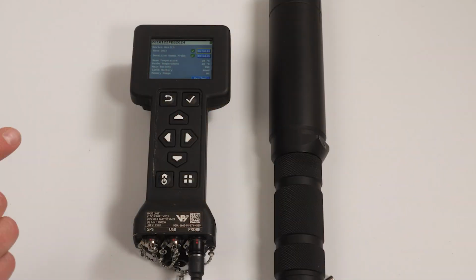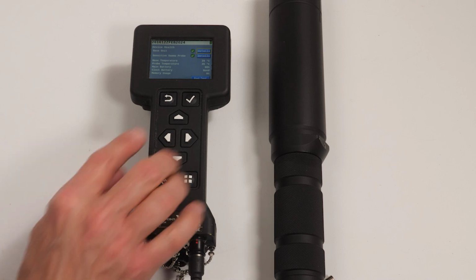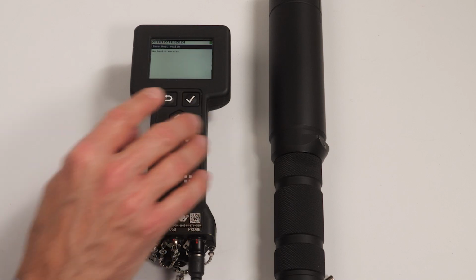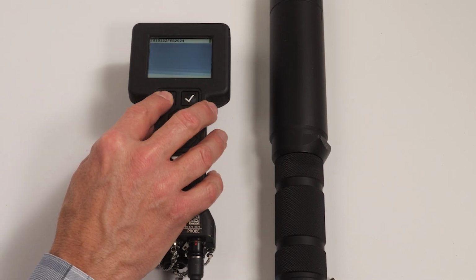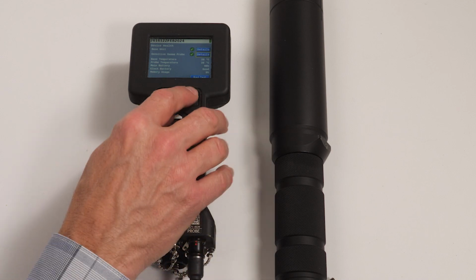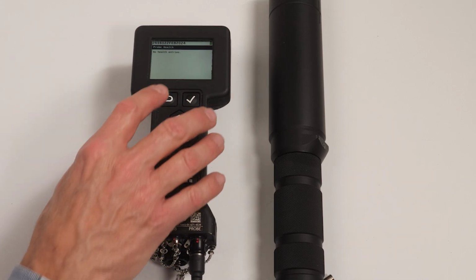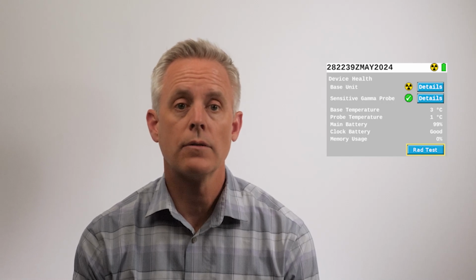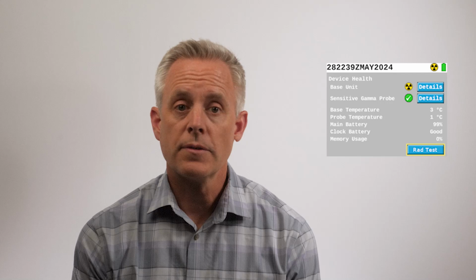The base unit health details button will be highlighted by default when you enter this screen. Press the enter key to view current alarm and system notifications. You can also view current alarm and system notifications for attached probes. The RAD test is meant to test both the low dose rate GM tube and the high dose rate GM tube to verify their functionality in the base unit before you go out to do a survey. If a probe is attached, the RAD test is used to test the detectors in the attached probe only. Probes must be detached to test the base unit detectors.